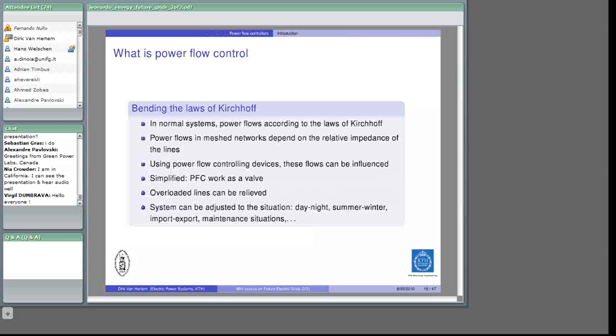When you use power flow controlling devices, you can influence these power flows throughout your system. Simplified, they work just like a valve. As a result, you can relieve the stress on overloaded lines and adjust the system according to the situation you want. You might want different operation for day or night, summer or winter, import or export, or in some maintenance situations a different system operation.